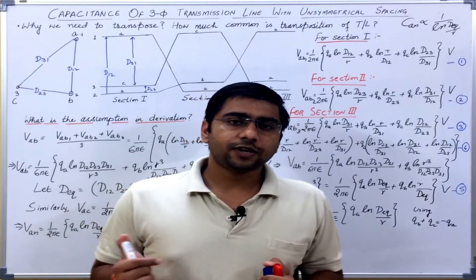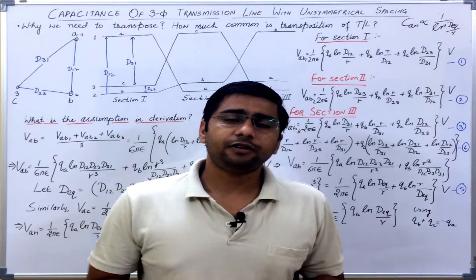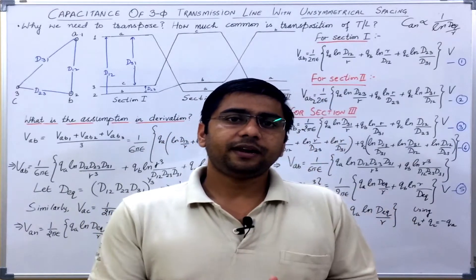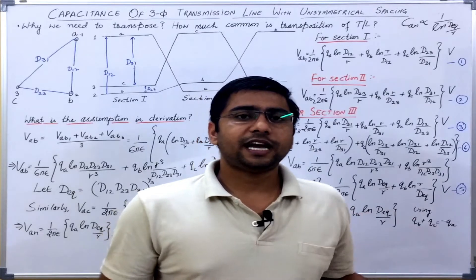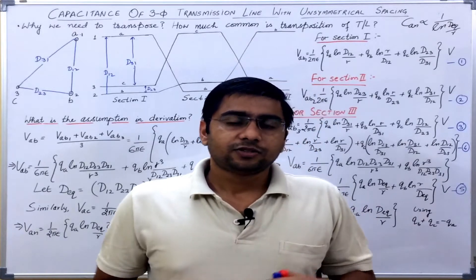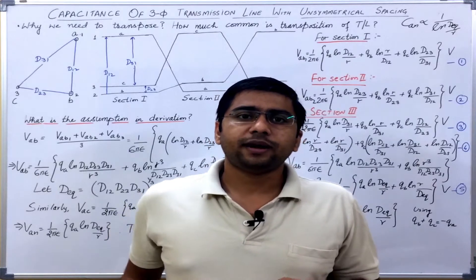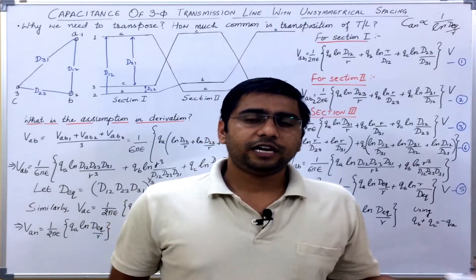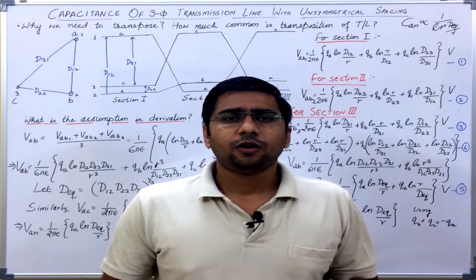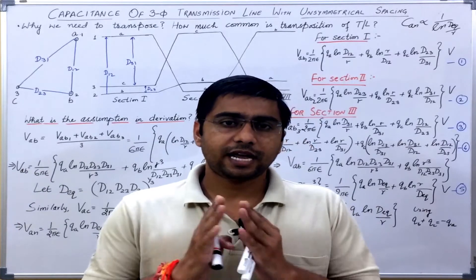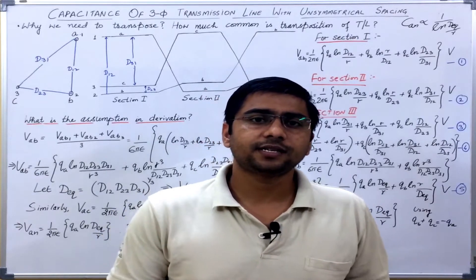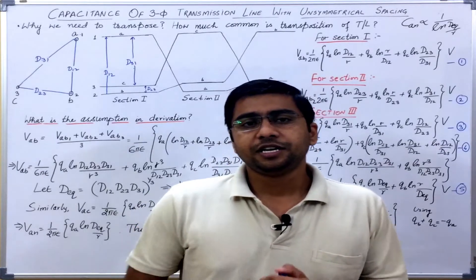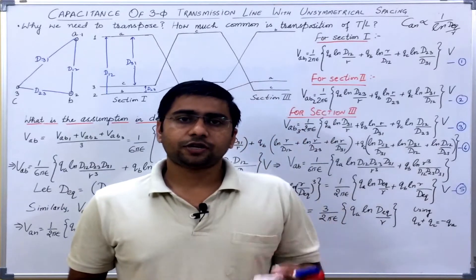What does transposition mean? As we already saw when we derived an expression for the inductance of a transmission line — if the spacing was not symmetrical, we transpose the line. Although practically it is not done very often; it is usually done only at switching stations or intermediate substations. We have also seen in our derivation of inductance for transposed lines that there was an image of a transposition tower, which is used for transposition. Similar towers are used for transposition only, but they are not very common.